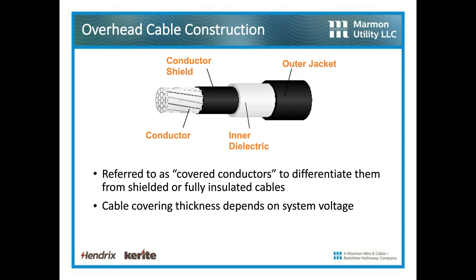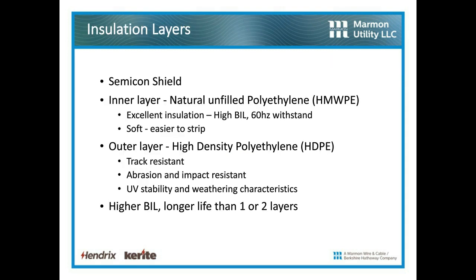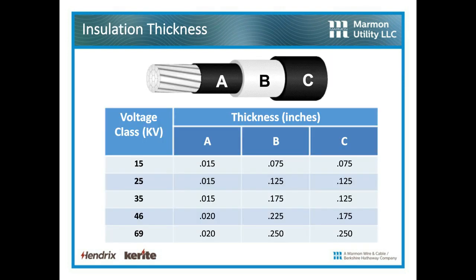Lastly, the outer jacket is going to be a high-density polyethylene. It's the highest density polyethylene we can source, with the anticipation that we need a very high abrasion resistance should we ever come into contact with trees. It's also where we're putting our UV inhibitor and our track resistant additive. And the thickness of that covering obviously is going to depend on the system voltage. Due to Ohm's law, if we have more voltage, we're going to need more impedance to limit that charging current on the surface.